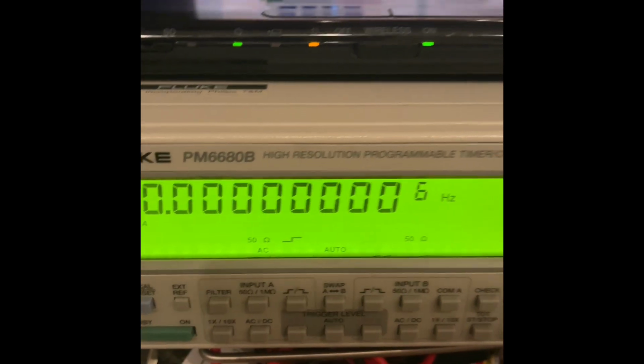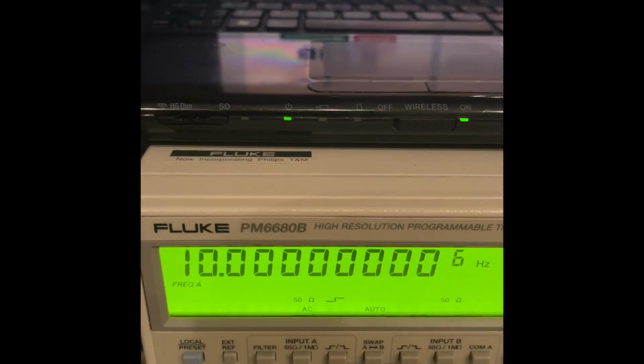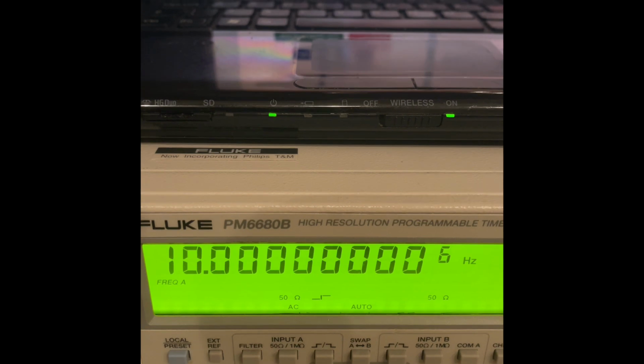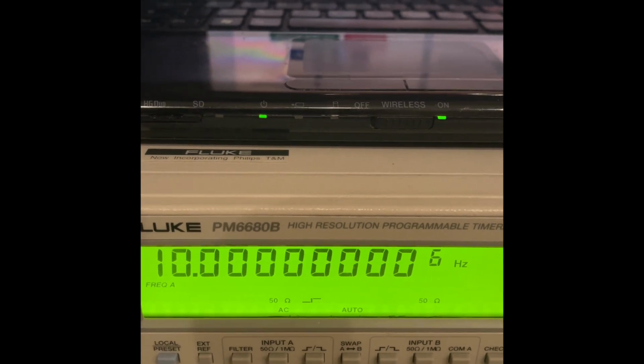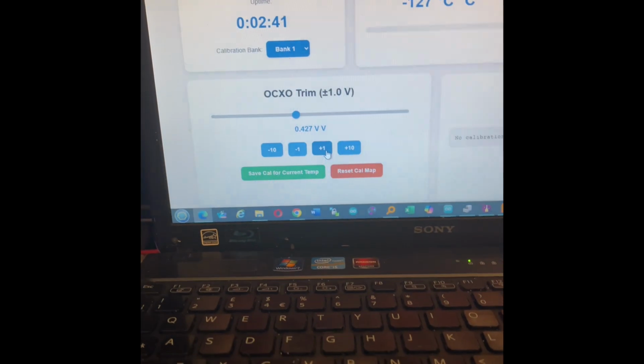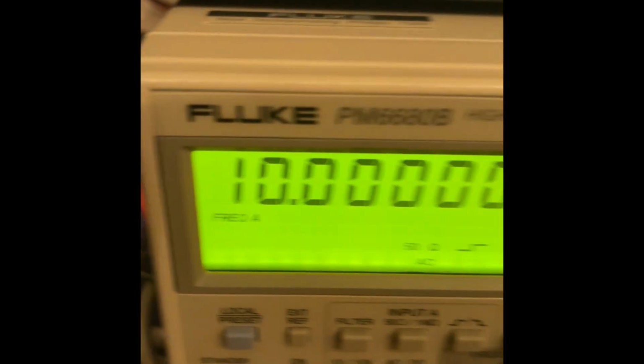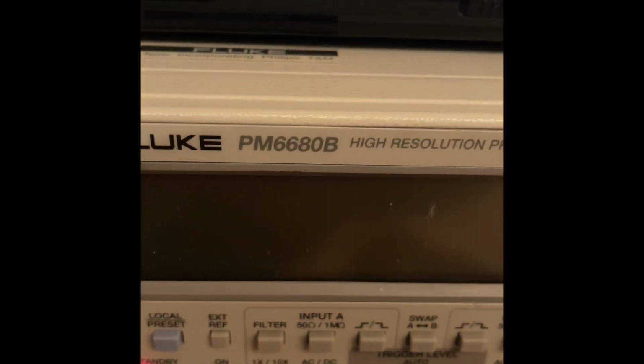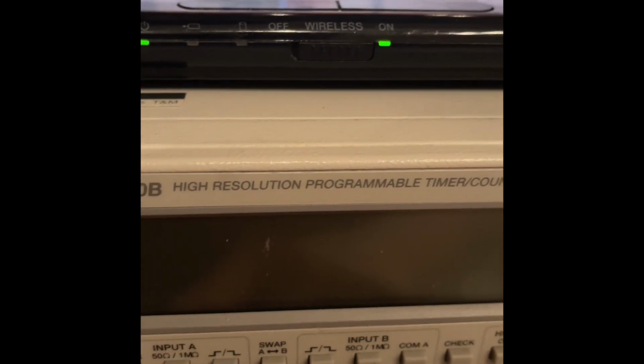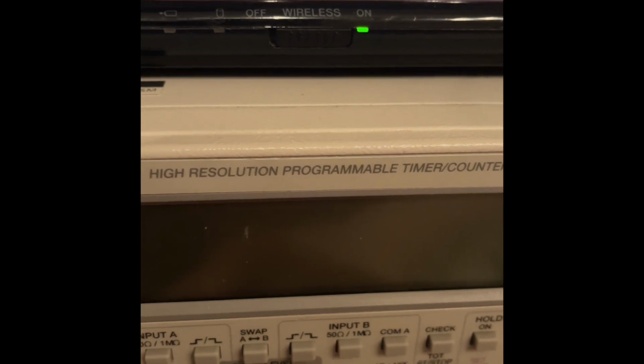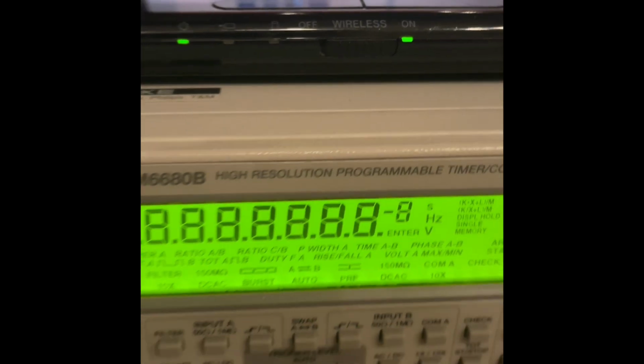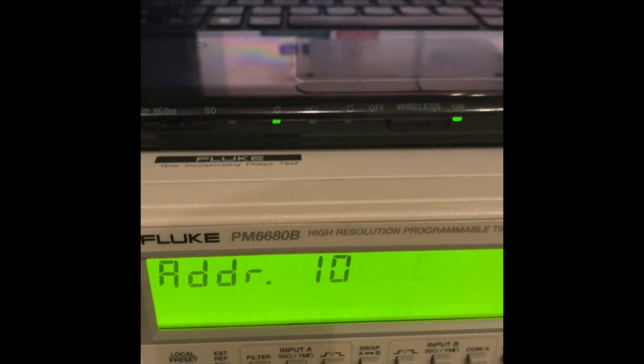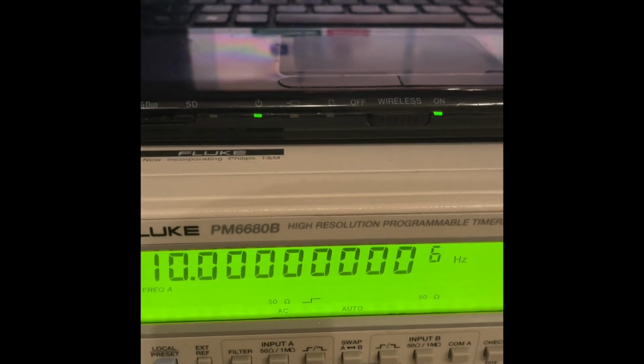So yeah, you never have to really flip the lid on one of these things ever again, and that is absolutely rock solid 10 megahertz, as sharp as the GPS though. This has not been on for very long. It's only been on for like 2 or 3 minutes, but already the temperature's up because this has got the standby. So when we turn this off, the power to the oven controlled crystal oscillator is constant. It's always on so long as this equipment's plugged in. So when we turn back on again, we should get an immediate 10 megahertz on the nose, which we do.